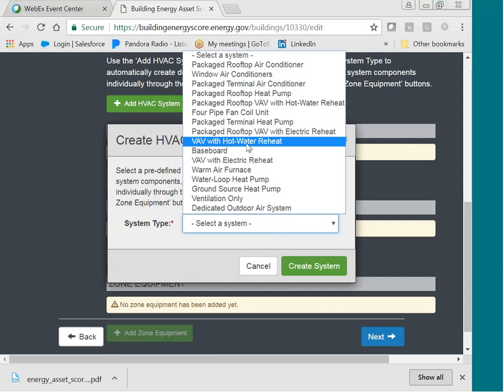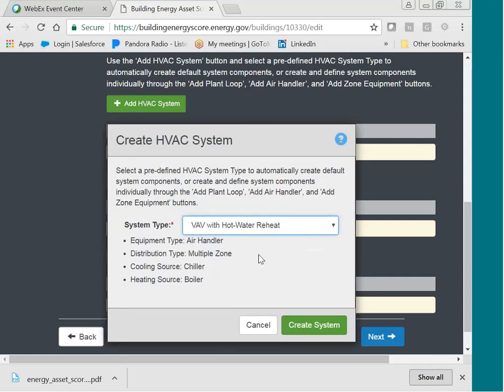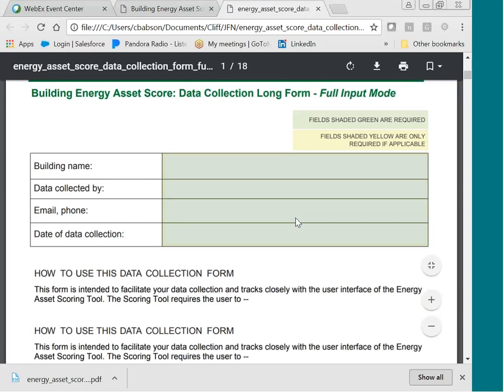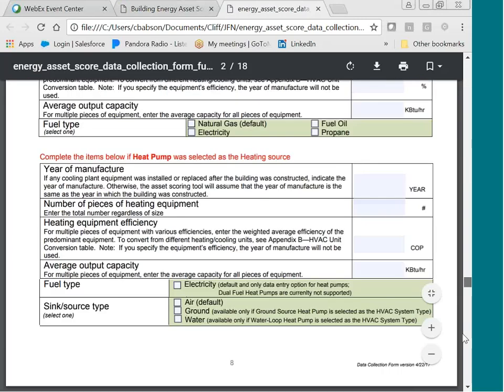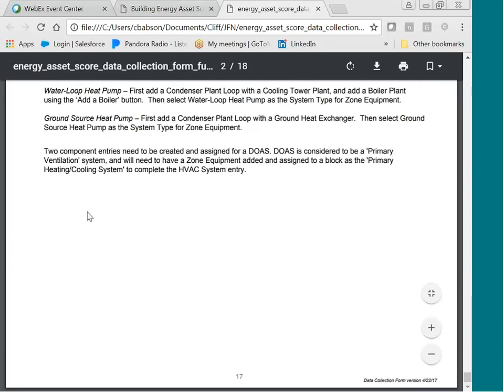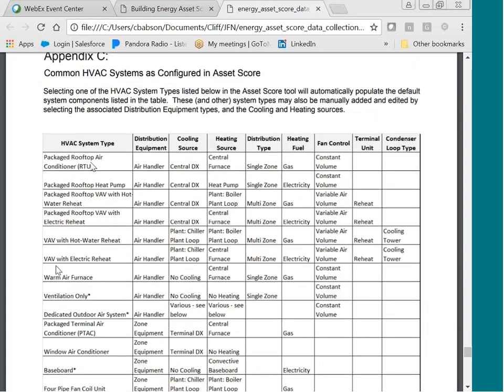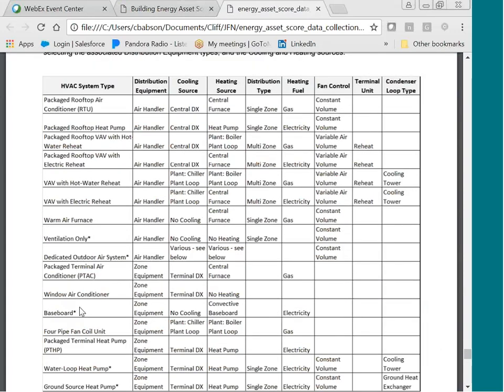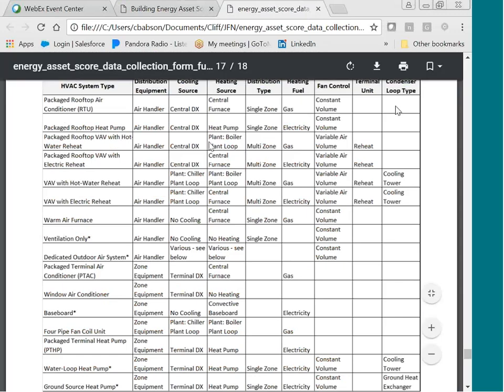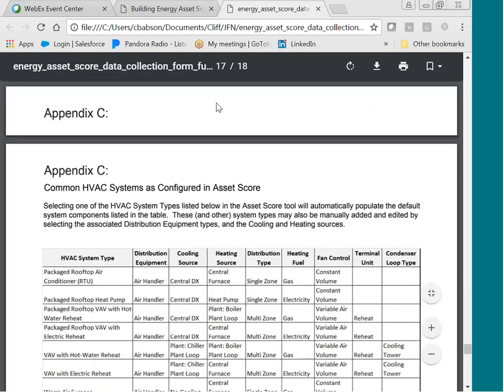So we're going to go ahead with a VAV, hot water reheat system. It's very common in commercial buildings. When we picked that system, it went ahead and built this equipment: air handler, distribution, multiple zone, cooling source, chiller. If you look at this data collection tool I showed you earlier, these are the types of systems in that drop down I just selected, and this is the equipment it will build automatically.